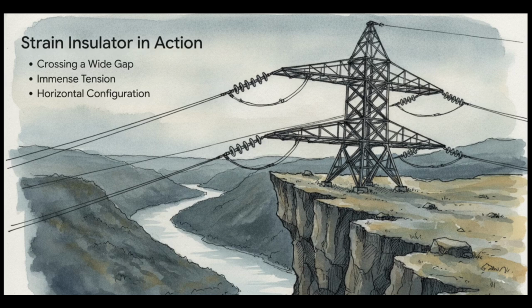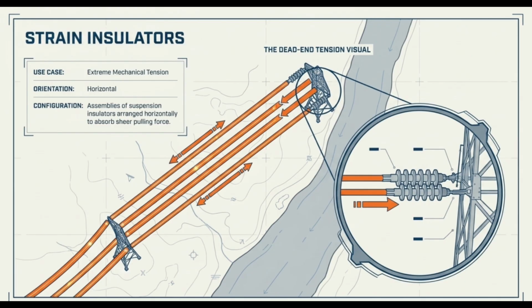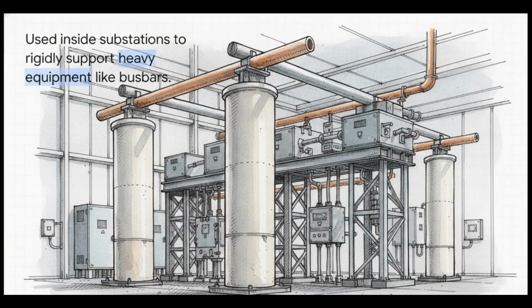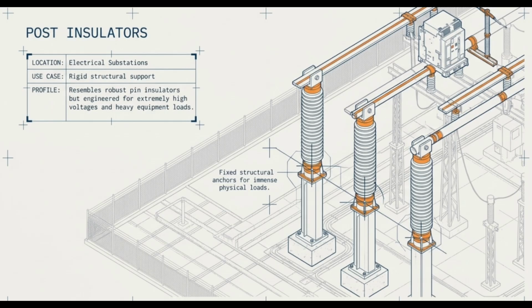So to handle this extreme physical pull, engineers use what are called strain insulators. These are essentially the exact same as suspension insulators, but they're pulled taut and configured horizontally rather than hanging down vertically. They absorb that extreme horizontal tension while still isolating the power. Meanwhile, the hardware changes all over again when the power finally reaches its destination. Inside those high-voltage electrical substations, where power is routed and stepped down for your home, we use post insulators.